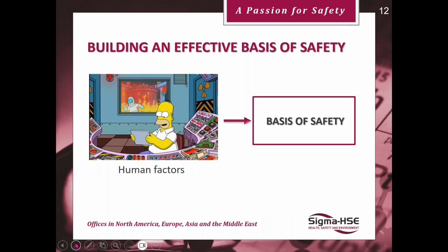One that I dealt with was two vessels, A and B. They were cleaning vessel A, and they switched off the ethanol, and while they were working, they started up the other process, which was process B. They pushed the button to let the ethanol in, and instead of that, it came into A. Someone had programmed it in wrong. And this is human factors. So sometimes they can be brilliant, sometimes they can do the most stupid, ridiculous things that you could ever think about. And I've certainly seen a few of those.